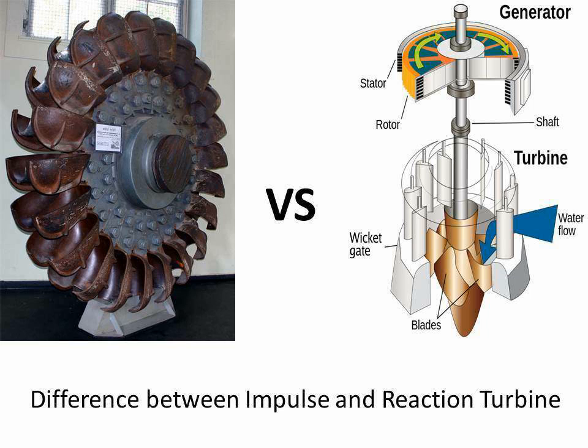Reaction turbines. In a reaction turbine, forces driving the rotor are achieved by the reaction of an accelerating water flow in the runner while the pressure drops. The reaction principle can be observed in a rotary lawn sprinkler where the emerging jet drives the rotor in the opposite direction. Due to the great variety of possible runner designs, reaction turbines can be used over a much larger range of heads and flow rates than impulse turbines.